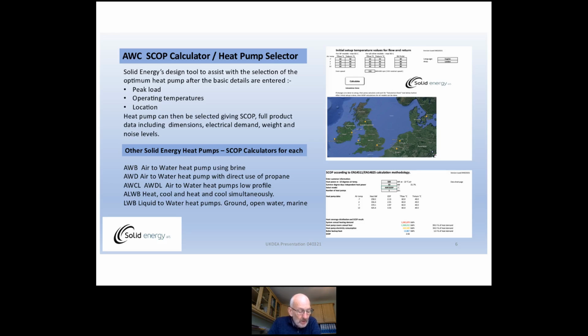Our AWB heat pumps use brine as the refrigerant medium when the compressors need to be located in the plant room with the coolers located at a distance. And we have the AWCL and the AWDL, which have lowest height profiles to keep planners happy. Our latest innovation has been a heat pump that can heat and cool simultaneously, and with commercial buildings in London apparently now have a greater cooling need in summer than a heating demand in winter, we can see that model being really important. We also manufacture large water source heat pumps, and importantly we have a calculator for all our models.